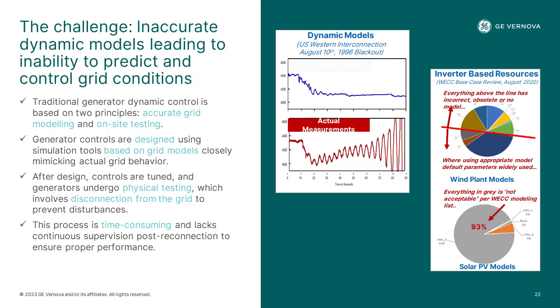So again, the need for having these models accurate is important. More recent, if we look at a 2020 case of the Western Interconnection, in this case, we are focusing on the renewables, so the inverter-based resources. The top pie chart shows the percentage of wind plant models that are inaccurate. The top half of the pie chart, 50% were, so everything above the red line were models that were either incorrect, obsolete, or were not using the right model. And of the remaining 50%, the bottom half and the blue portion, a majority of them were using default values. So again, they weren't reflecting the actual physical asset that was there.